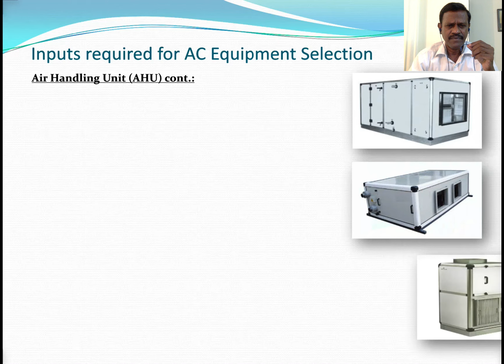For the fan selection, you have to specify what fan outlet velocity you want. See, actually here the supplier will play around. They will select the fan velocity around 15 meter, 18 meter per second, like that, to reduce the cost. So you should be very careful. You limit the fan outlet velocity and inform the vendor to select accordingly.